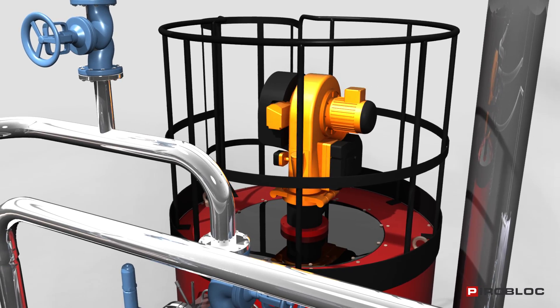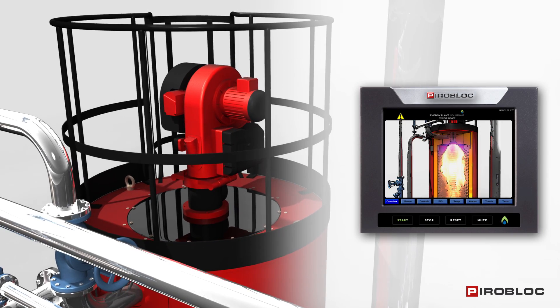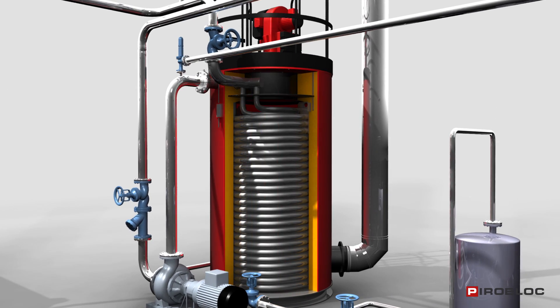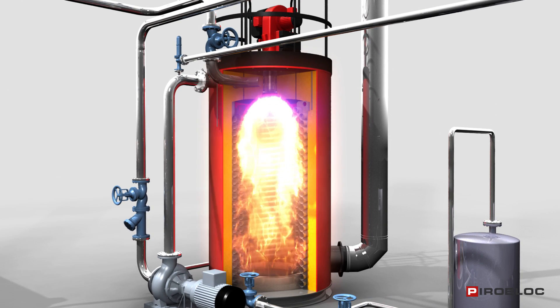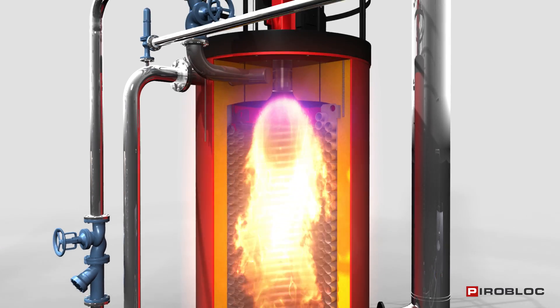The burner is switched on and we select the desired operating temperature on the touchscreen of the electric cabinet. The burner with modulating power adjusts itself accordingly to the set temperature by regulating the gas-air mixture in an appropriate way. A boiler of three effective smoke passages achieves a yield of around 90%.